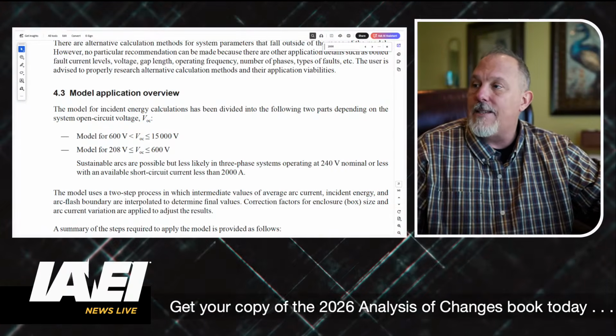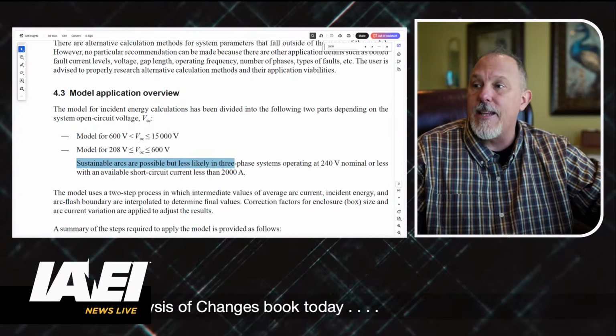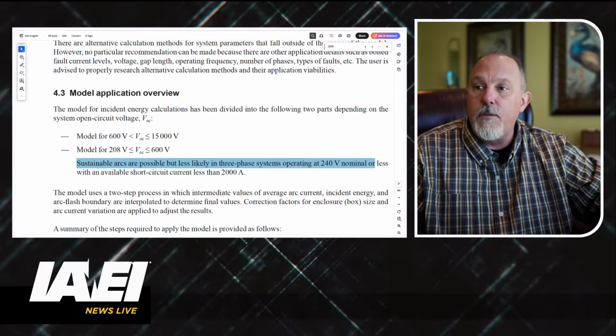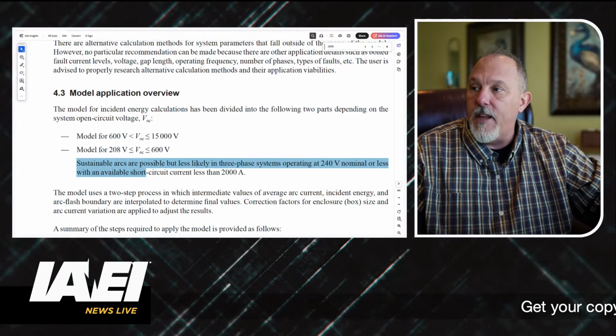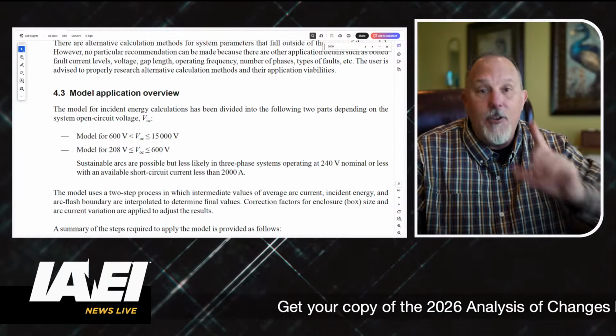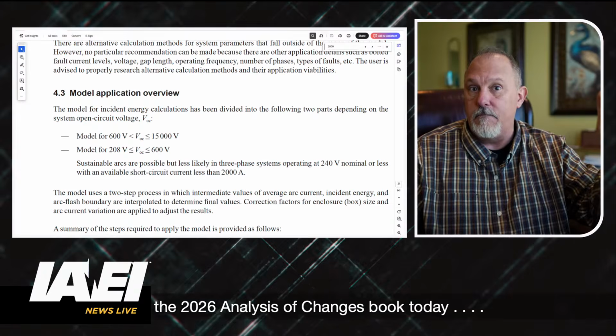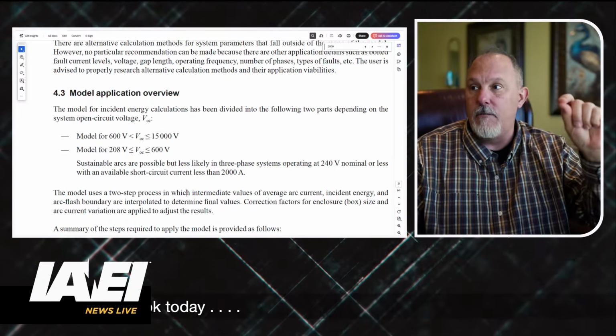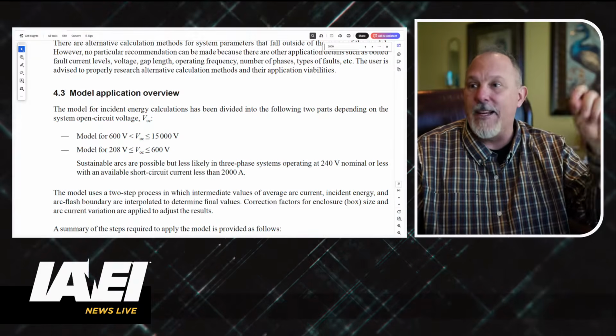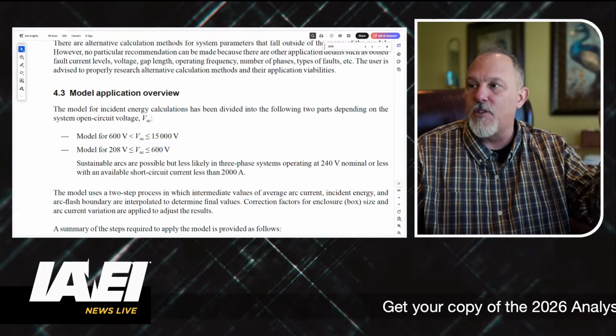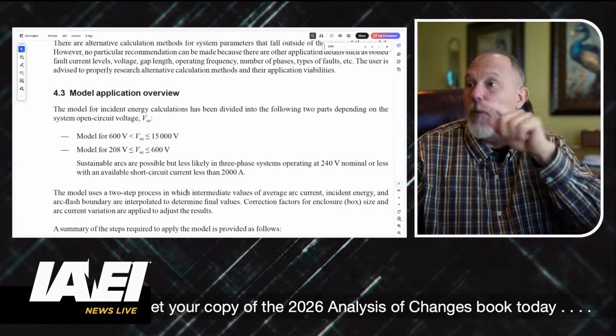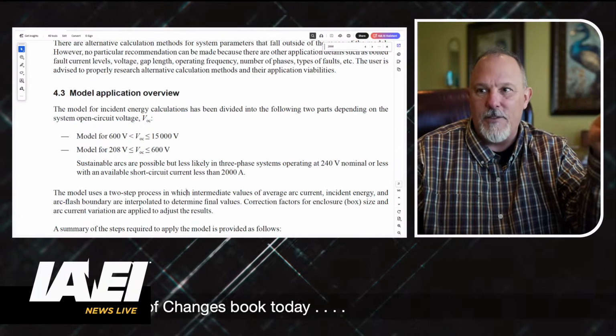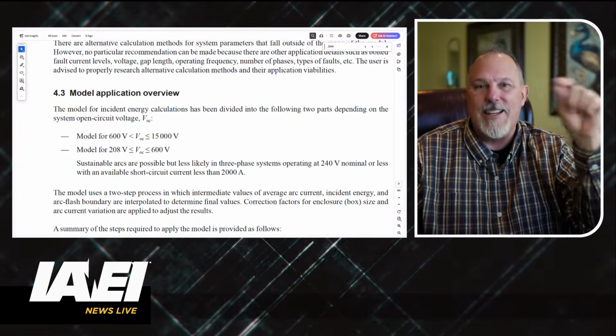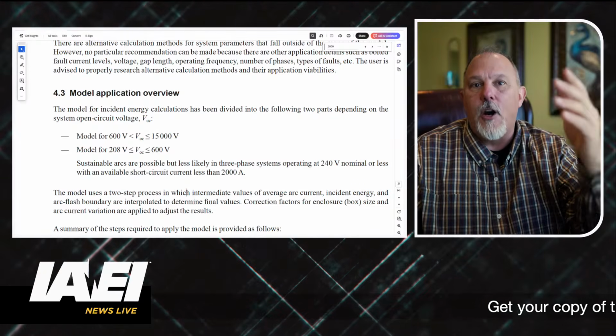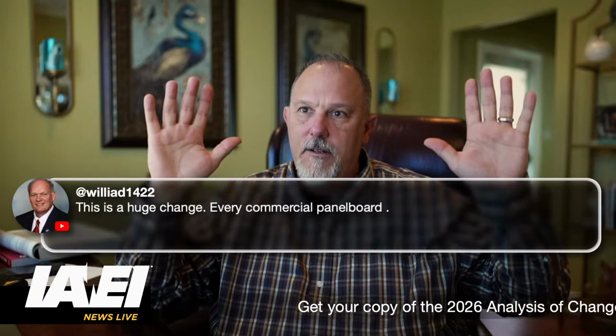But it says sustainable arcs are possible, but less likely in 3-phase systems operating at 240 volts nominal or less with an available short circuit current less than 2,000 amps. I don't know about you, but that sounds like an exception. Exception: 3-phase systems operating at 240 volts nominal or less with an available short circuit current less than 2,000 amps. Equipment operating at 240 volts nominal or less, with an available short circuit current less than 2,000 amps, are not required to be marked.